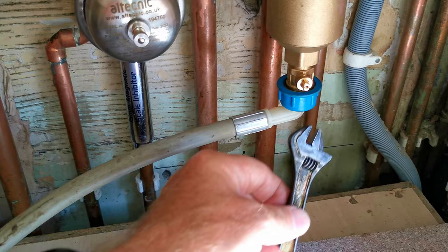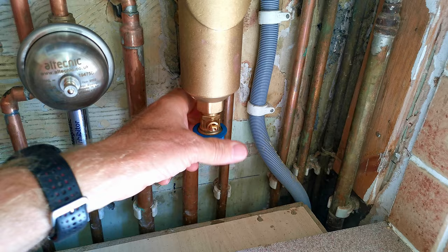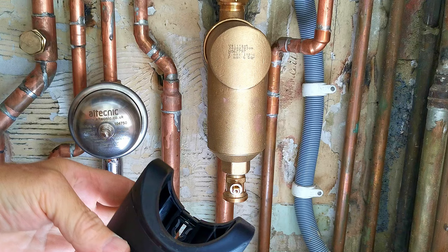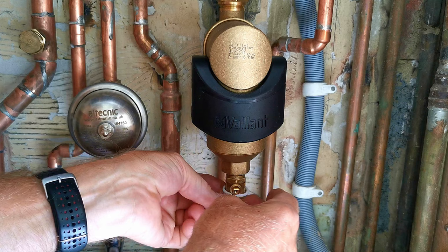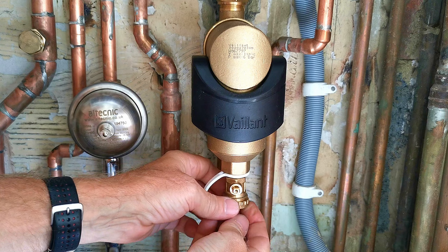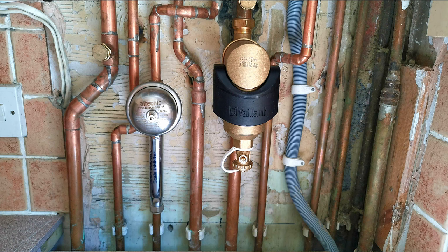You might want to think about adding more inhibitor after cleaning your filter — I've made a video on how to do that. Once you're happy there's no more magnetite coming out, close the valve and remove the hose. Then replace the magnet by pushing it up onto the filter until the clip engages. Put the little rubber piece on the cap first so you don't lose it, then screw the cap back on. Make sure you haven't lost the little rubber seal, as without it the valve may drip. And there we go — the Vaillant filter is cleaned out.